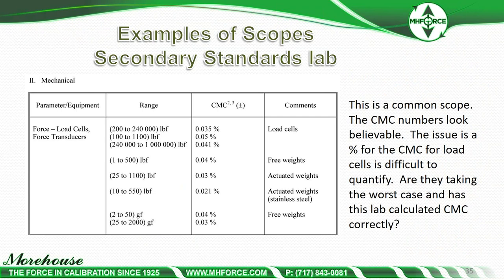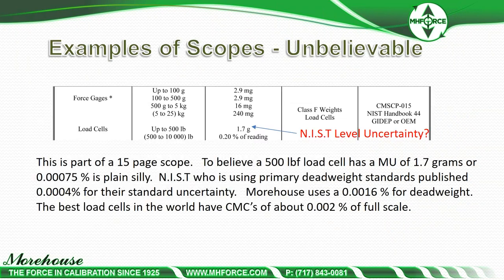Here's a more common scope — the CMC numbers look believable. The issue is that the percent CMC for load cells is difficult to quantify. Has this lab calculated CMC correctly? We have no idea. It looks pretty believable, but there are no notes telling you what they're doing.